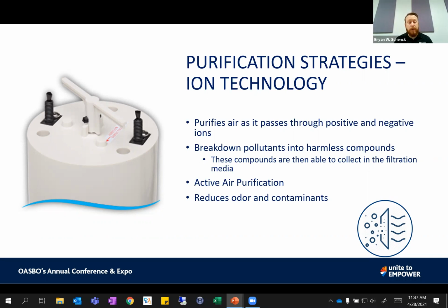What needlepoint bipolar does is completely electronic—it provides positively and negatively charged ions into the air at the molecular level. Those ions get attracted to opposite polarities, and those compounds agglomerate. They're attracted to each other, connect, and strip away the harmful products they need to survive, leaving byproducts like oxygen and hydrogen. They also become larger as they attract each other, so they can be filtered out through our air systems and typical filtration in mechanical equipment. Because these ions go into the space and through the ductwork, actually cleaning outside of the mechanical equipment, that makes them an active air purification strategy.